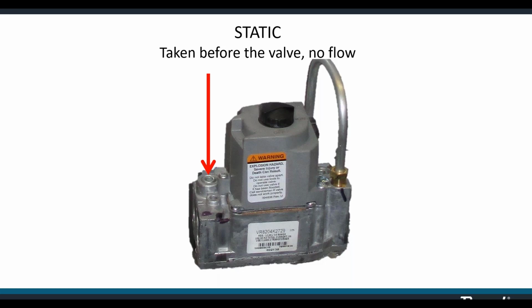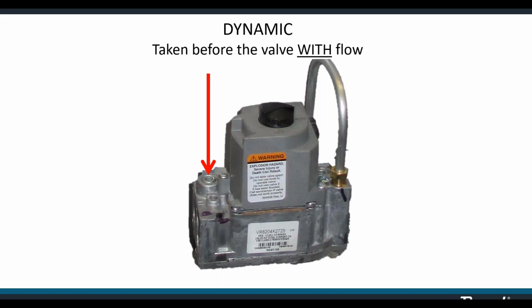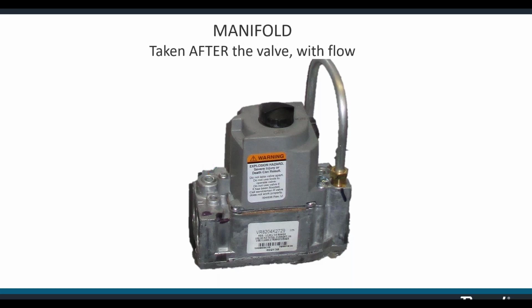Leave your manometer in place and fire your heater. That will give you the dynamic pressure taken before the valve with flow. So this is the pressure while the heater is burning. Finally, you'll cap that back up and move your manometer to the test port on the right in order to take the manifold pressure. This is taken with flow after the valve. This is the pressure of the gas that's going to the burners.